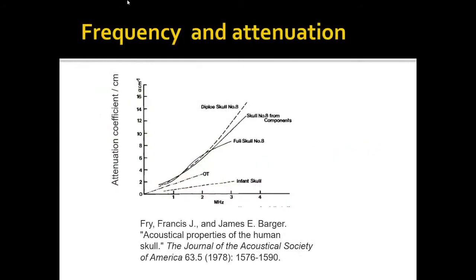When you look at frequency versus attenuation studies, which have been simulated numerically and also experimentally verified as far back as the 70s, we see a clear linear relationship between increasing fundamental frequency and how much attenuation, or acoustic loss, you get from the skull. This is exactly why most fundamental frequencies have stayed in this range, to minimize the attenuation coefficient and the amount of losses, which leads to a lower power output being required from your transducer.